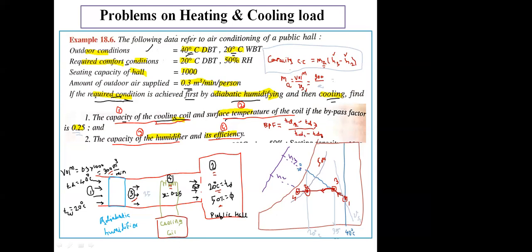That formula will be correct if your coil is at the first position. But here, if you see, the coil inlet point is point number 3, coil surface temperature or coil condition is point number 4, and the outlet point for that coil is point number 2. So here whatever bypass factor will be there, that will be in terms of TD2, TD3 and TD4. Are you getting it? Yes.